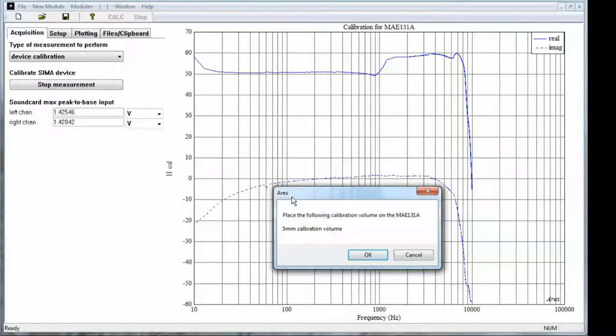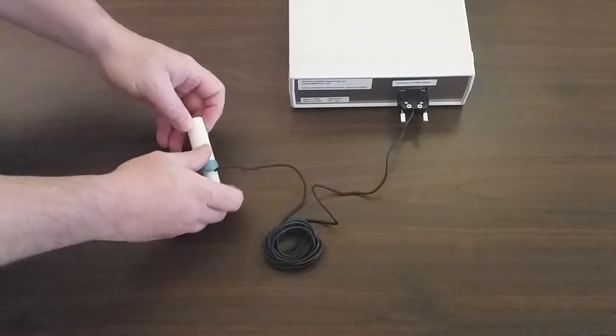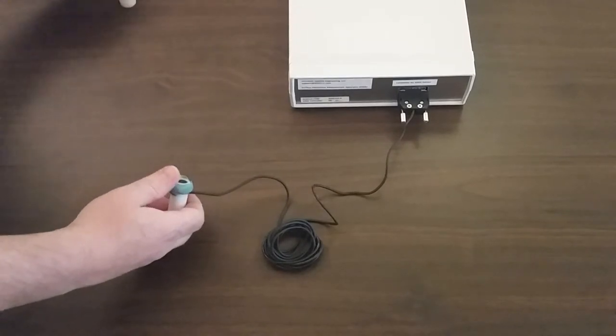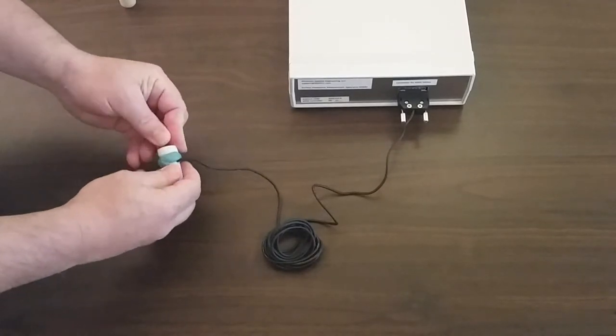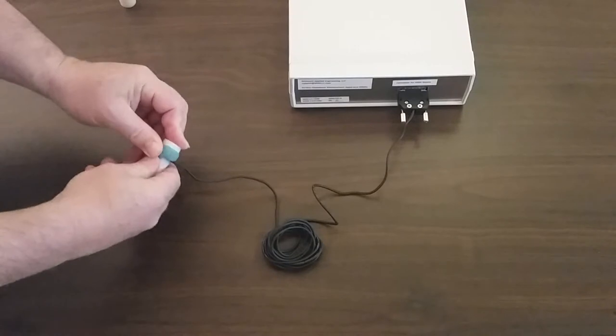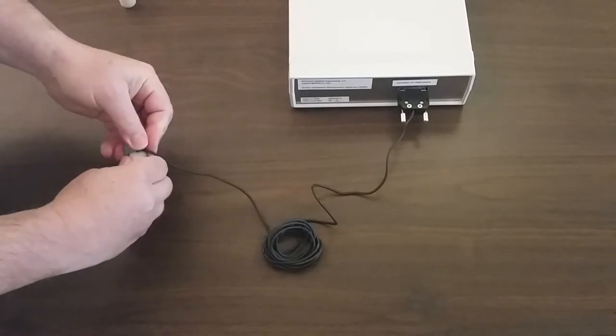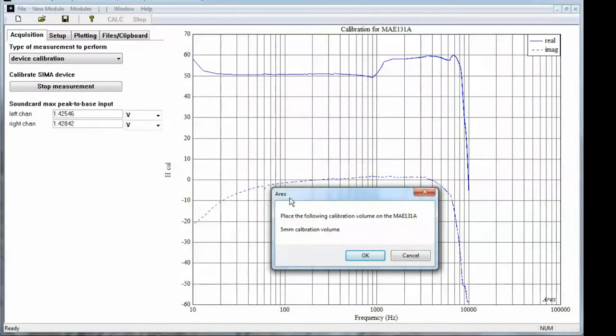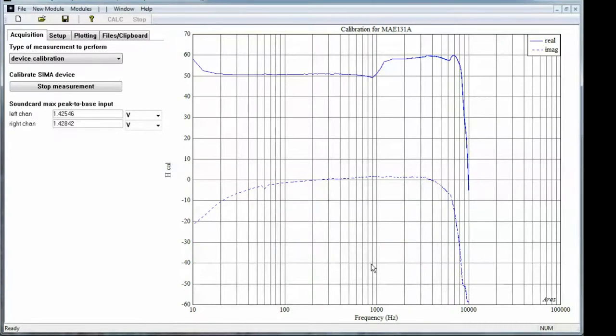OK, it's performed the 50mm calibration and it's now asking for the 5mm calibration volume. So we'll come back over and take the 50mm off and put the 5mm calibration volume on. Go back over to ARES and press OK. You'll hear a higher frequency sweep as it does the 5mm calibration.